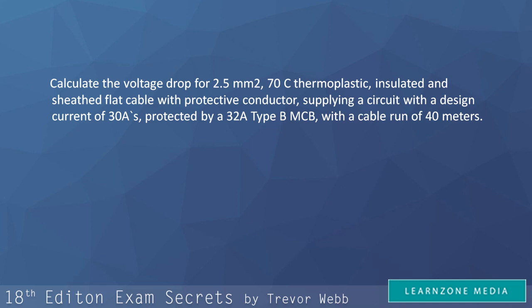In other words, a 2.5 millimetres square flat twin and earth cable has voltage drop of 18 millivolts per amp per metre. So this is our first value that we can insert into the formula.